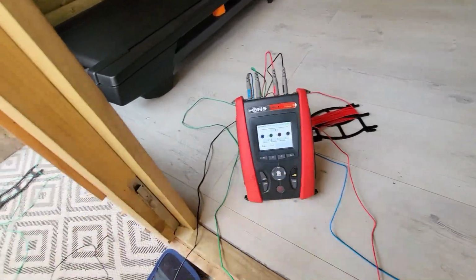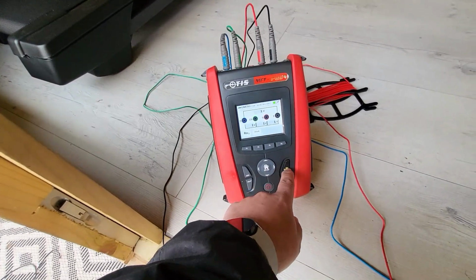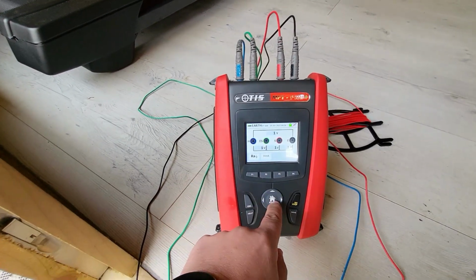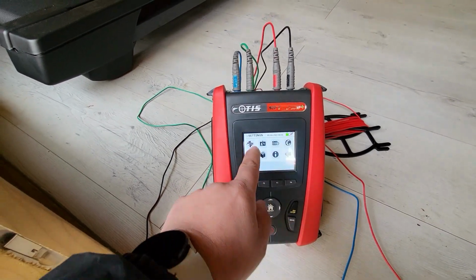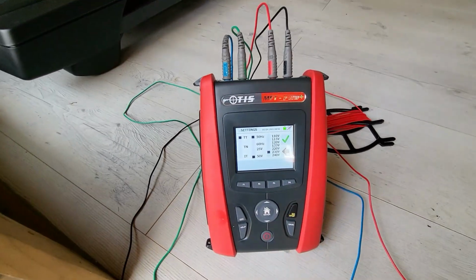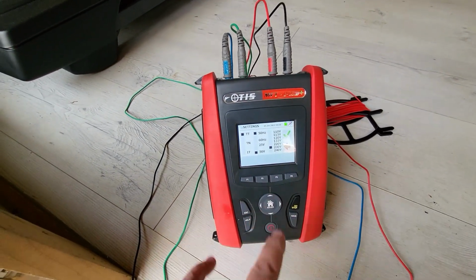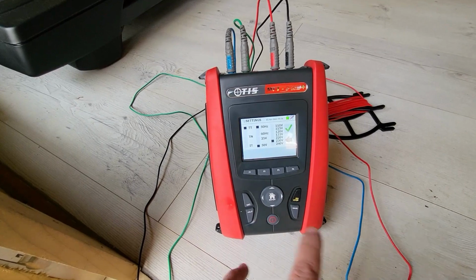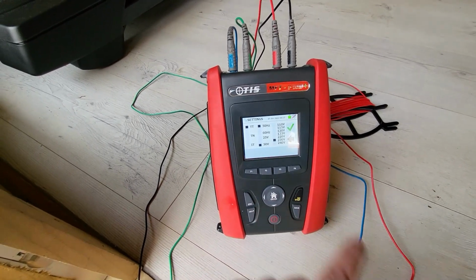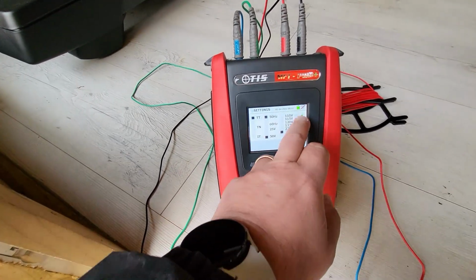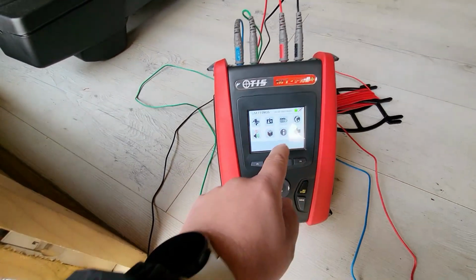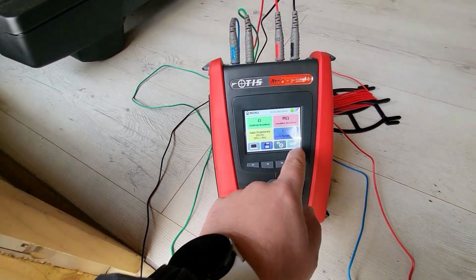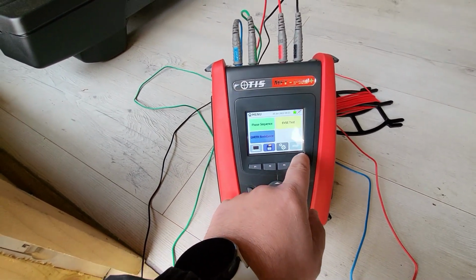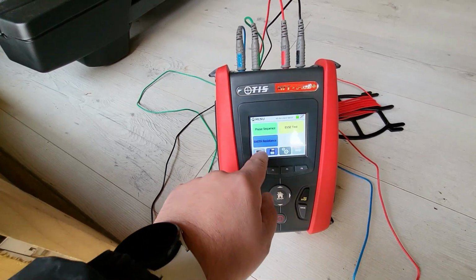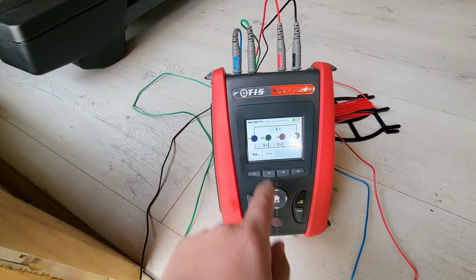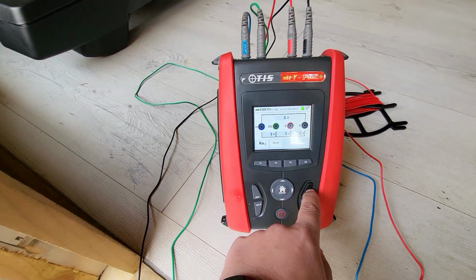Not really Cooper, but if we hit test, you'll see here - if I take you through the TIS itself, if you go into settings, you can choose if you're on a TN or a TT system. It doesn't really change the way the test's done, but it presents the result in a different way, and I'll show you that later on in this video as an example. But for now we'll leave it on TT. I know this isn't a TT install, before people get upset with me about that - it's just an earth electrode on a TN-C-S system, but people often just refer to it as TT.